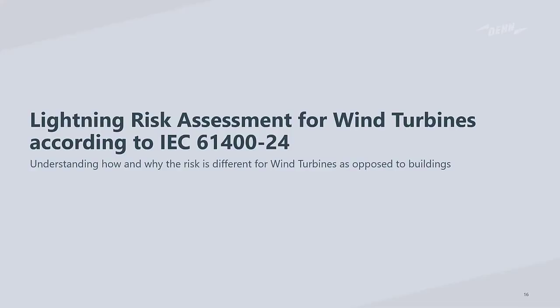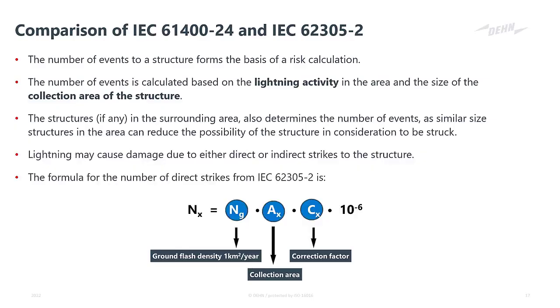As I mentioned, the lightning protection standard for wind turbines has a special method in IEC 61400-24 for calculating risk for lightning strikes onto wind turbines. Now, to discuss that, we have to take a step back and go to the standard 62305 part 2. As I mentioned in the beginning, this was the first standard from IEC to calculate risk due to lightning, and it was focused on structures and buildings. This is a very comprehensive standard, and all the other industries take the majority of their calculation methods from the standard. So the 61400 standard for wind turbines was formed on the basis of 62305 part 2.